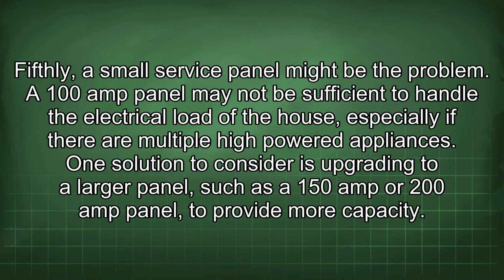Fifthly, a small service panel might be the problem. A 100 amp panel may not be sufficient to handle the electrical load of the house, especially if there are multiple high-powered appliances. One solution to consider is upgrading to a larger panel, such as a 150 amp or 200 amp panel, to provide more capacity.